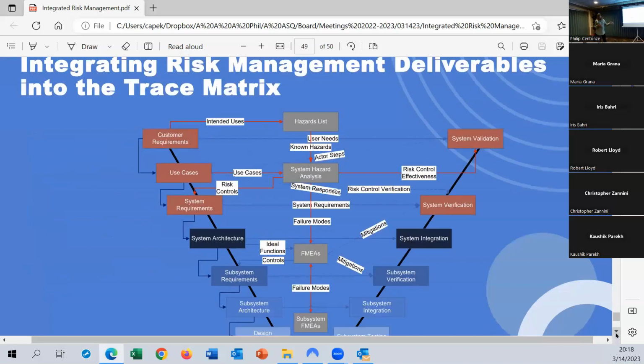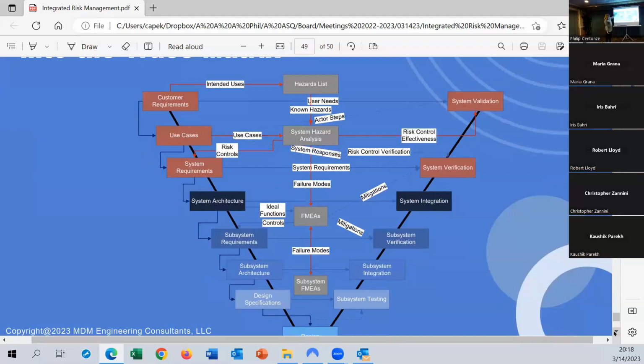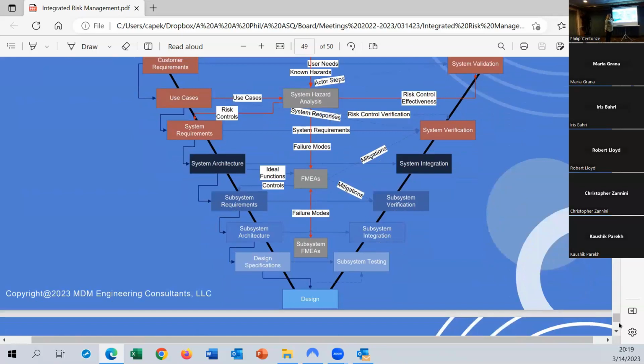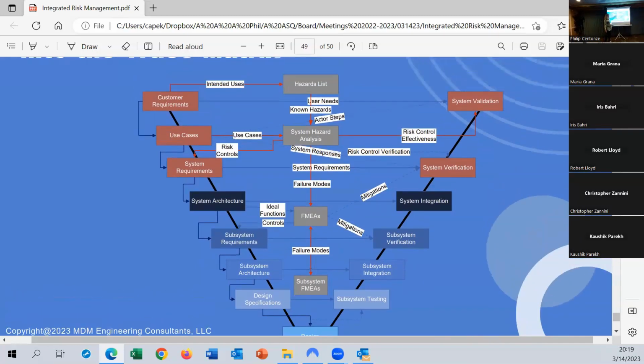So this is the typical verification and validation V, right? We have requirements on this side. Typically, you will have customer requirements or user needs, and you do use cases and system requirements. So we start elaborating on the design as we go. And then on this side of the V, testing at every level. Well, in that V, I like to put all of the risk documents in the middle, because I take my intended uses that are typically documented in my user needs or customer requirements. That's going to drive the list of hazards that I'm going to have to worry about. So I use those hazards for my system hazard analysis.